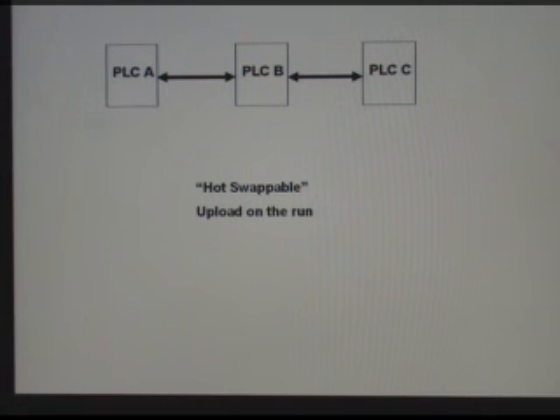So it sounds like it's a pretty reliable system. You have to have some voting between them. And when 2 out of 3 agree, that's what happens. And if you don't get 3 out of 3, the operators are alerted that something's wrong with the control system. They're hot swappable, which means that if this PLC were to fail, you could go ahead and pull it out. These two would still control the equipment, and then you could put a new PLC card in, upload the program to it, and then bring it online, and it would then start talking and comparing answers with the other two.